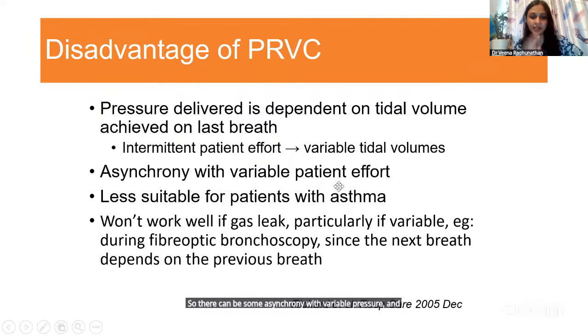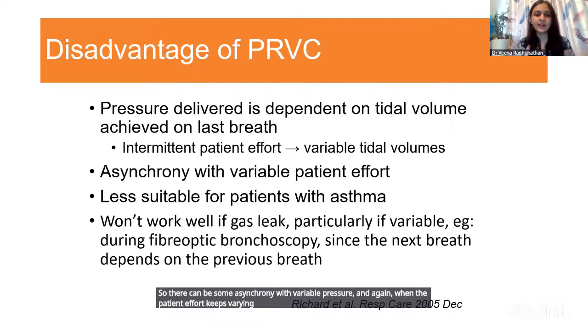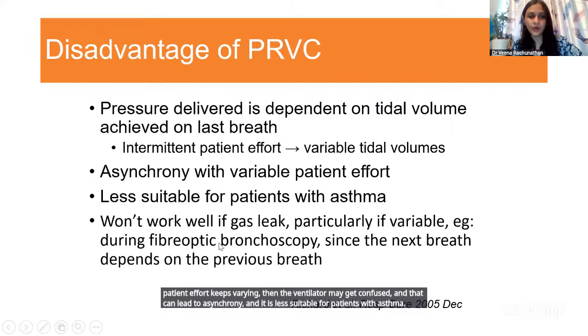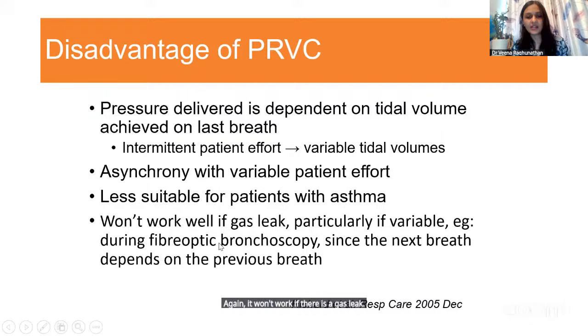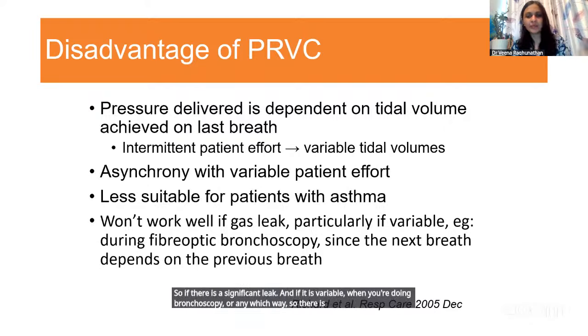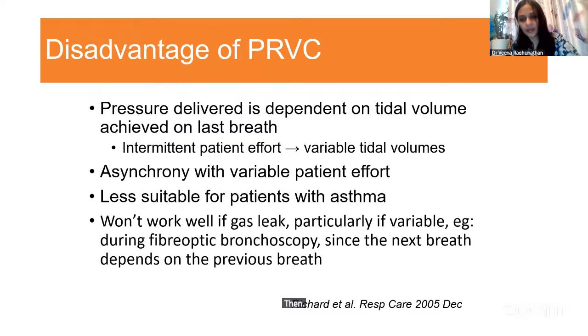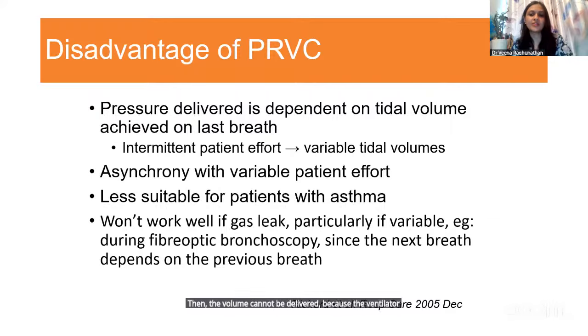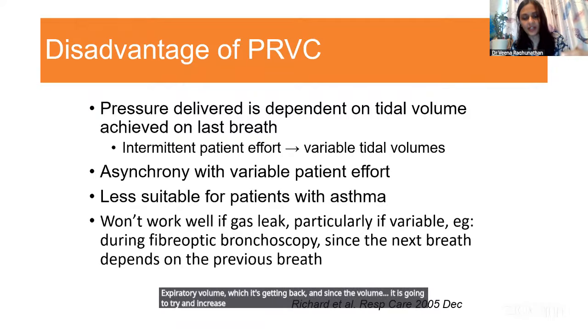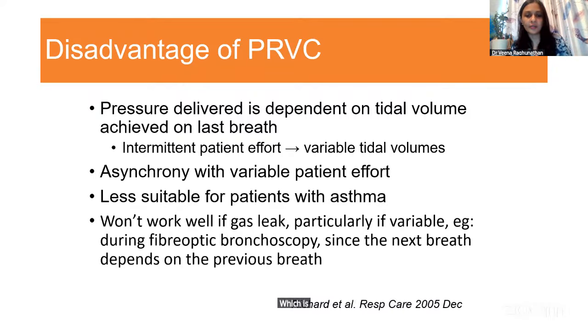And again, when the patient effort keeps varying, then the ventilator may get confused and that can lead to asynchrony. And it is less suitable for patients with asthma. Again, it won't work if there is a gas leak. If there is a significant leak, and if it is variable, when you're doing bronchoscopy or in any other situation, then the volume cannot be delivered, because the ventilator is going to judge the expiratory volume which it's getting back. And since the volume is low, it is going to try and increase the pressure every time, which is actually not what the patient requires.